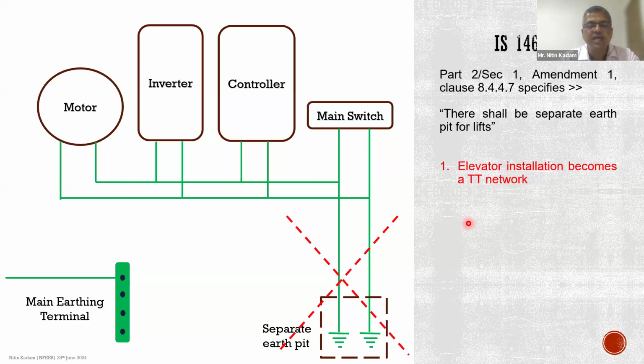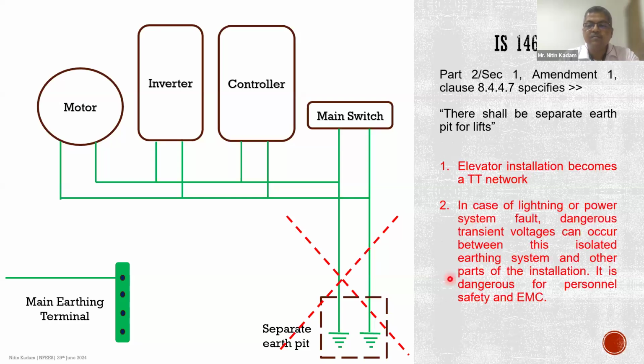And this could be a potential hazard for the people who would be touching the equipment in case of fault. It could also create a fire hazard. It is also, in case of lightning or power supply system faults, there could be dangerous transient voltages that can occur between this isolated earthing system and other parts of the installation. And it could be dangerous for the technicians who are working on the site. So this concept should not be used in the case of elevators.